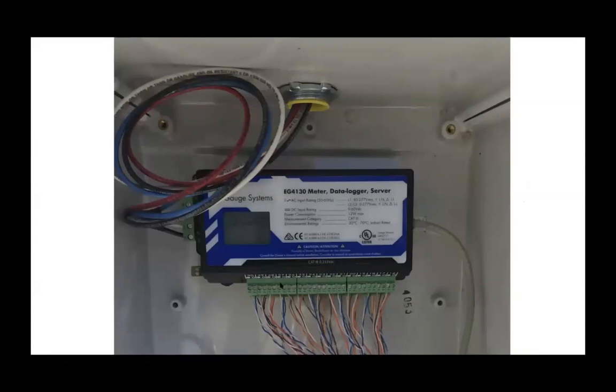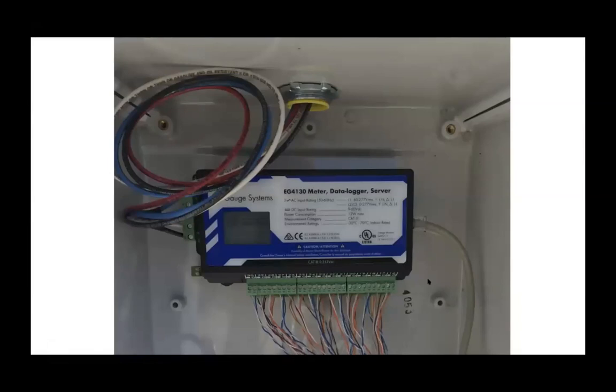There is a core model that just has 15 inputs. You can also install more than one eGauge at a site. Electrical wires coming in on the left provide the device power, as well as voltage readings, and then your typical internet connection allows the data logger to send the information it collects from the site to your online user interface.